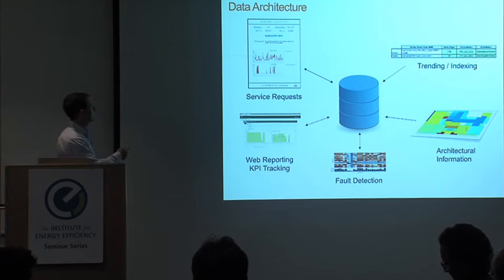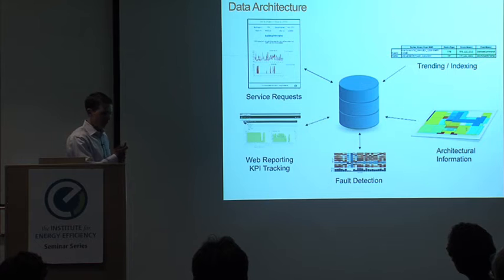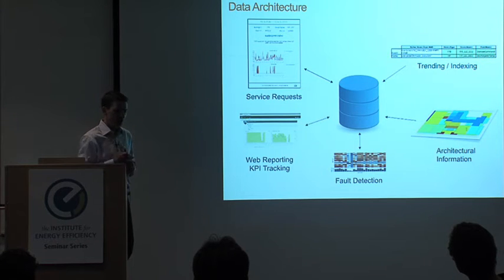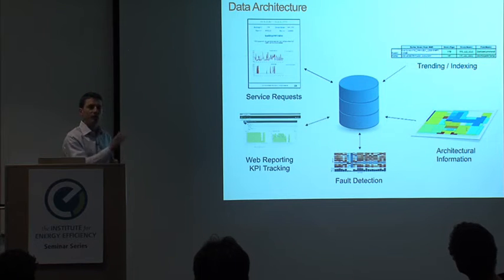This still requires a human filter to say, okay, this fault is worth sending a technician out for. But when we do send them out, they'll have trend data showing exactly what's going on and what's feeding into the fault - is it a thermostat offline, or a valve stuck in a certain position? This arms them with the information to go out once and fix exactly what's wrong, maybe even before the work order is put in.